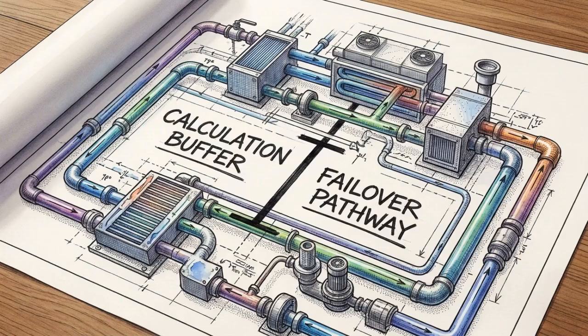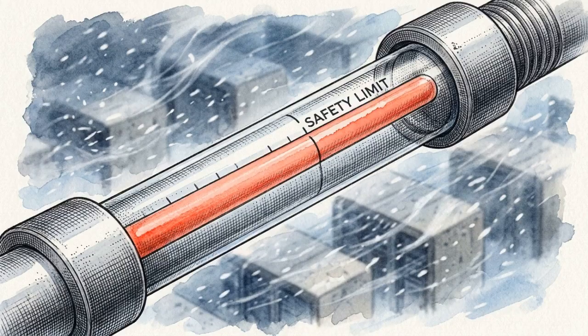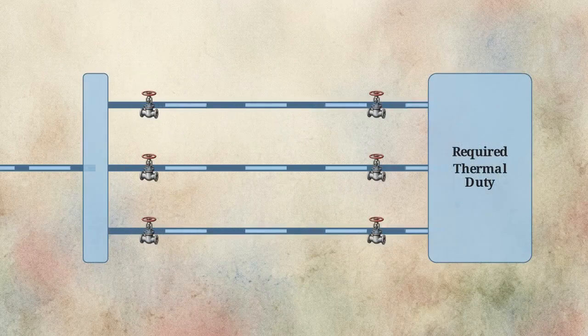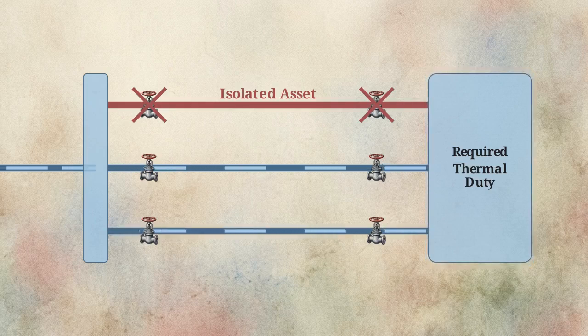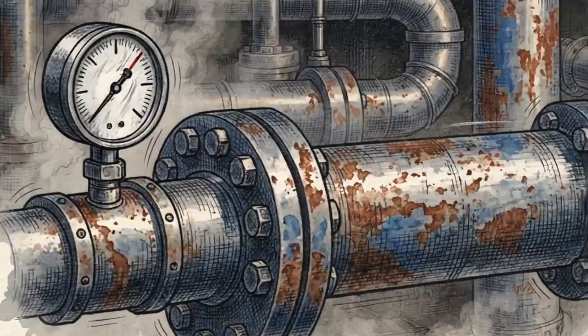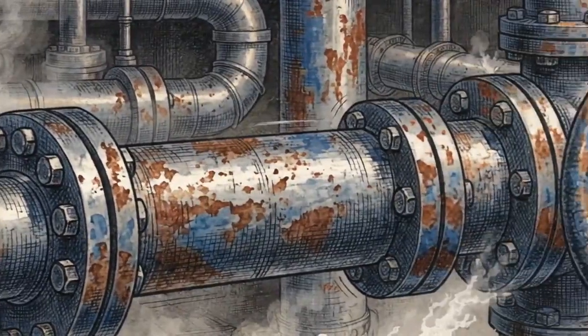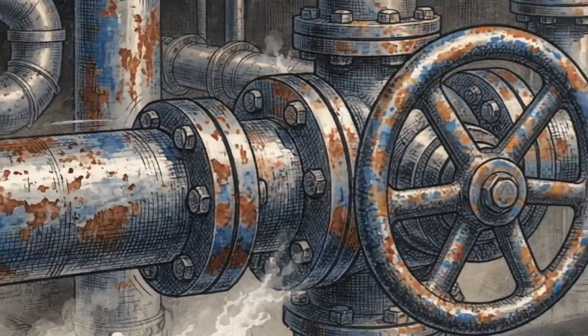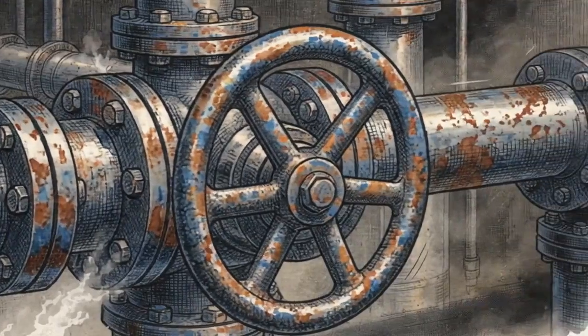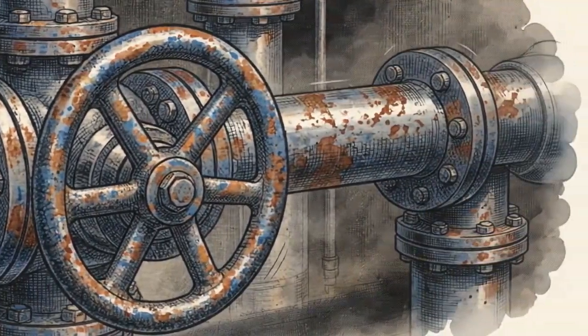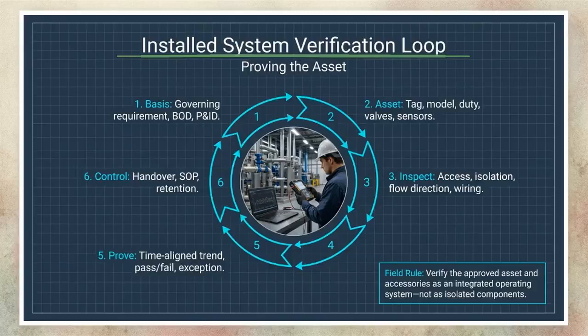When sizing these systems, engineers separate design margin from physical redundancy. Margins account for calculation uncertainty and extreme weather conditions. Redundancy determines exactly how an asset can be isolated for service without losing the required thermal duty. Every single interface requires an explicit owner, a testable acceptance criterion, and a precise restoration rule to verify these boundaries hold under extreme pressure.